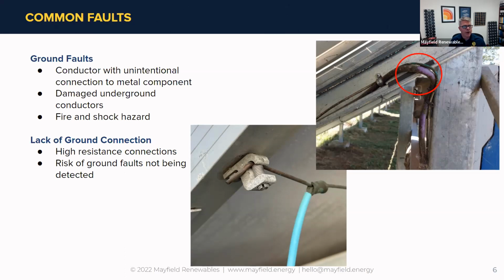Ground faults are conductors that have an unintentional connection to a metal component. Here we show a picture on the top right of a conductor wrapped around a piece of metal that's clearly been installed for a while, with potential for that conductor to rub against the metal and create a connection. This can happen on day one, for example when modules are put down on the racking system and someone torques down a connection, causing a ground fault right then, or it can happen later down the line. That's what we'll focus on: this unintentional connection to grounded conductors or components.